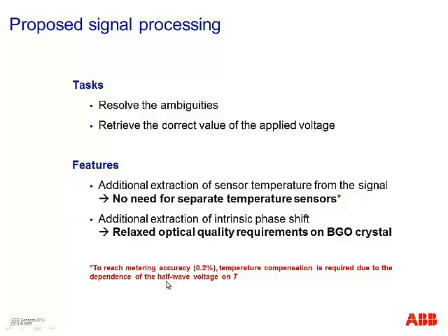This is needed because if you want to reach metering accuracy, which is 0.2% of the rated voltage, you need temperature compensation, since the variation of the V pi voltage shown before is bigger than 0.2%. So you need to compensate for that.